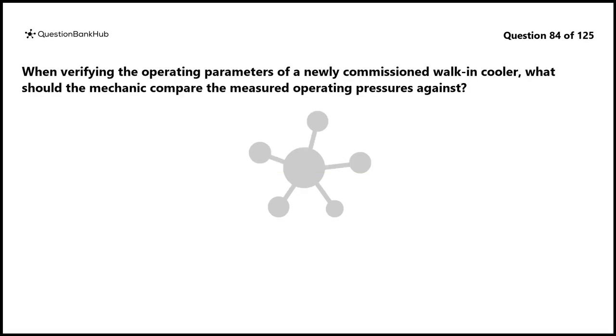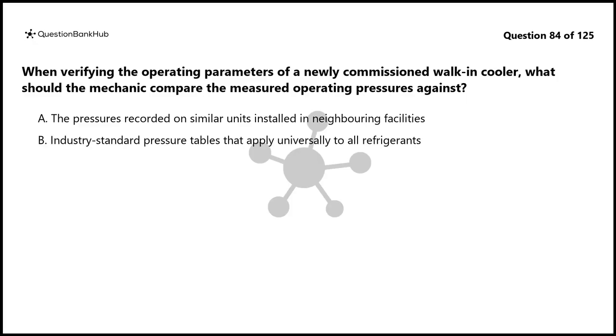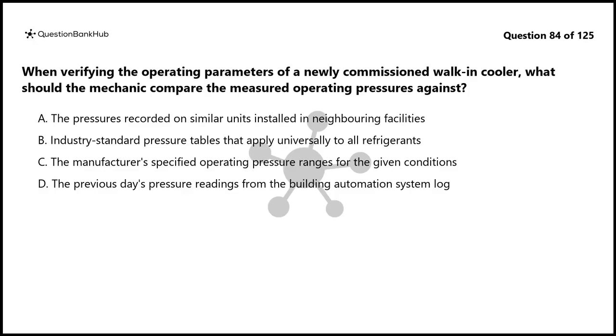Question 84. When verifying the operating parameters of a newly commissioned walk-in cooler, what should the mechanic compare the measured operating pressures against? A. The pressures recorded on similar units installed in neighboring facilities. B. Industry standard pressure tables that apply universally to all refrigerants. C. The manufacturer's specified operating pressure ranges for the given conditions. D. The previous day's pressure readings from the building automation system log.